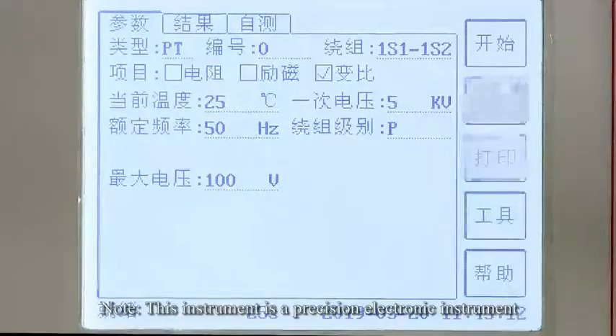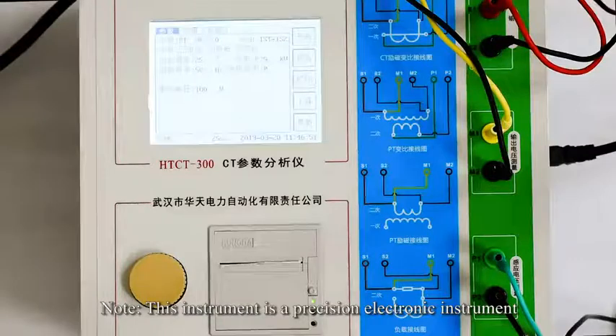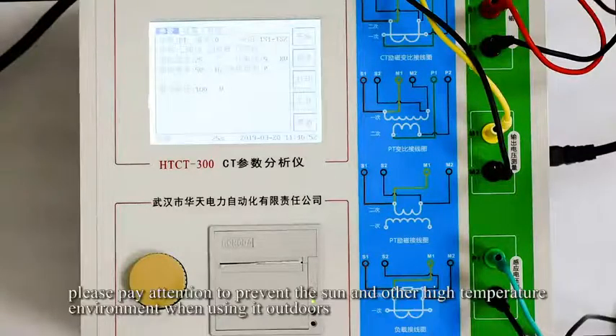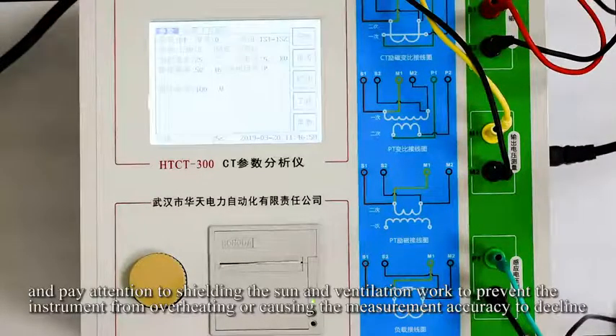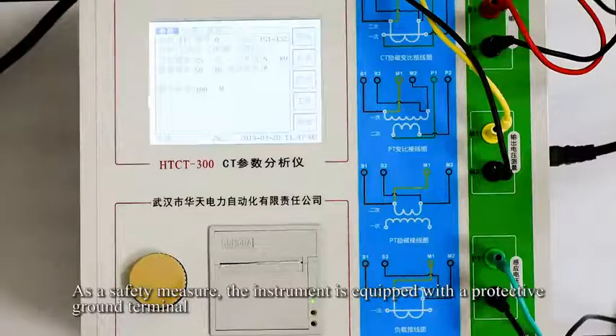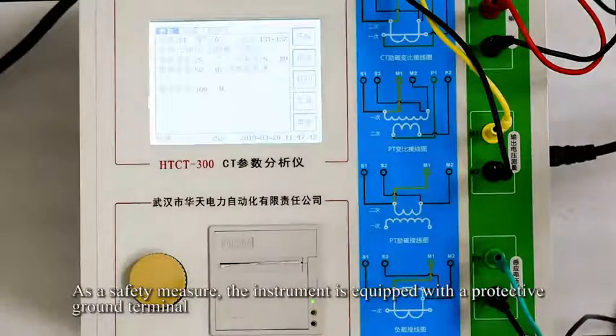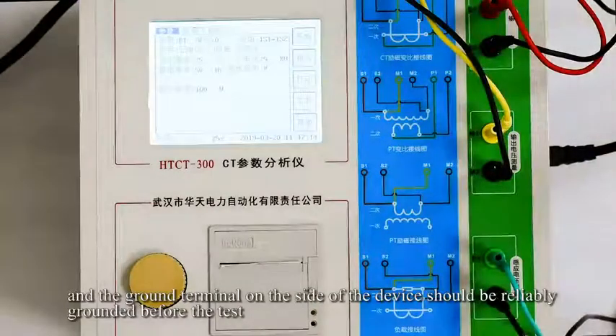Note: this instrument is a precision electronic instrument. Please pay attention to prevent the sun and other high temperature environments when using it outdoors, and pay attention to shielding the sun and ventilation work to prevent the instrument from overheating or causing the measurement accuracy to decline. As a safety measure, the instrument is equipped with a protective ground terminal, and the ground terminal on the side of the device should be reliably grounded before the test.